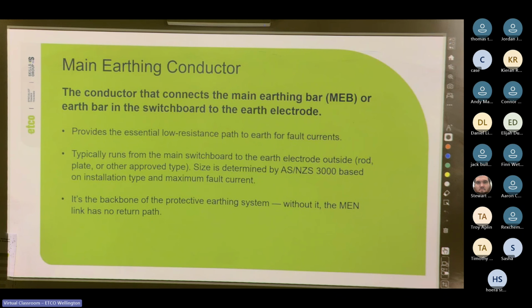Yeah, so sometimes you can have an earth plate or an earth grid or an earth mat. Some of the generators have a giant kind of mesh, almost fields of copper buried under the ground. And what tends to happen when they install them is they have to dig up the ground, put down the copper mesh mat, and then they have to quickly bury it again because obviously, with a giant field of copper, people are going to have a field day.